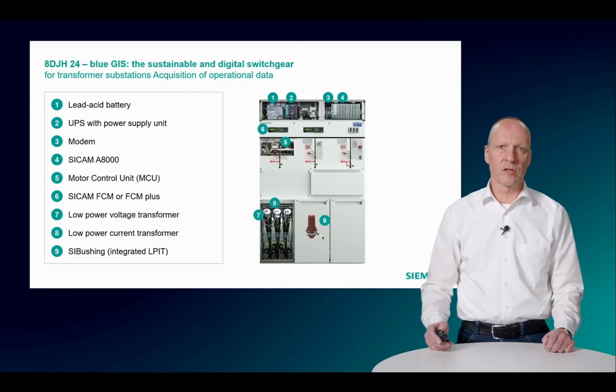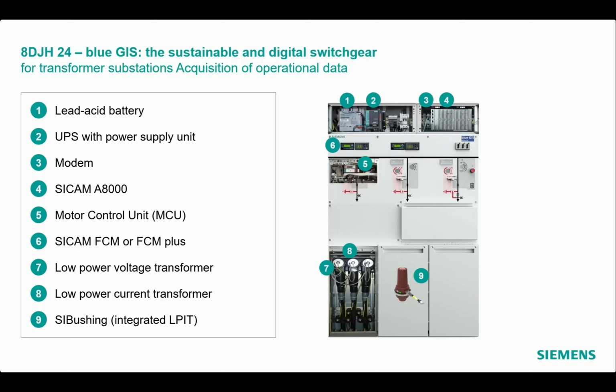Looking at the cable connection compartment, we have installed instrument transformers, mainly so-called LPITs, which means low power instrument transformers, for measuring the voltage and the current. These LPITs deliver analog signals, which will be converted into digital signals in the connected short circuit and earth fault indicator. These digital signals can then be transferred to the gateway and subsequently to the cloud or into the SCADA system. We have managed in the meanwhile also to integrate the current and voltage measuring in our cable connection bushing and released already the so-called SIBushing, which I will explain later in detail.